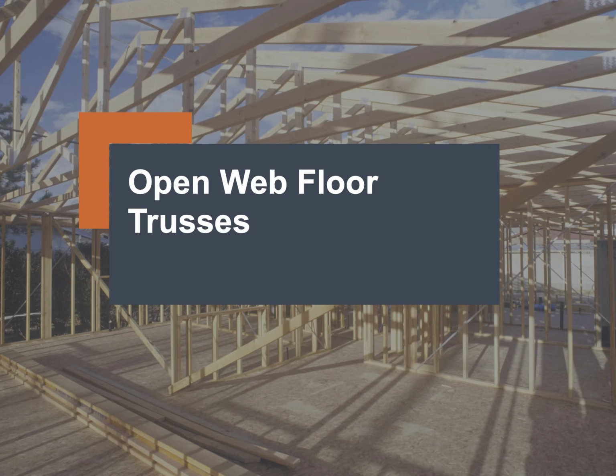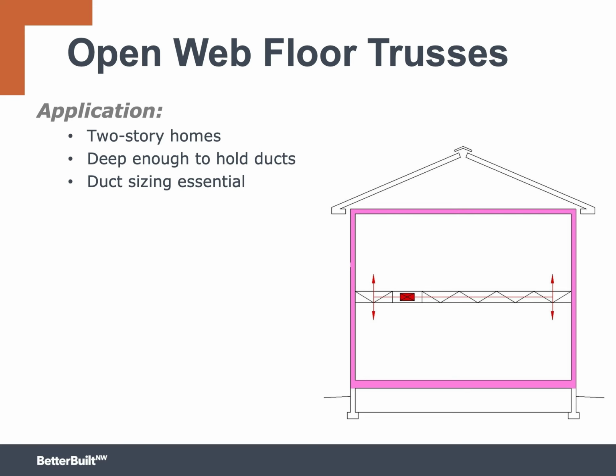Perhaps the most popular strategy for ducts inside is the use of open web floor trusses. Let's take a look. Open web floor trusses can be the most flexible ducts inside approach for two-story homes. With a centrally located furnace, ducts can easily run to any spot in the house. The biggest issue is truss depth. Most homes now use a 12-inch joist for a second-story framing. Depending on the duct design, the depth necessary may increase to 14 or even 16 inches.